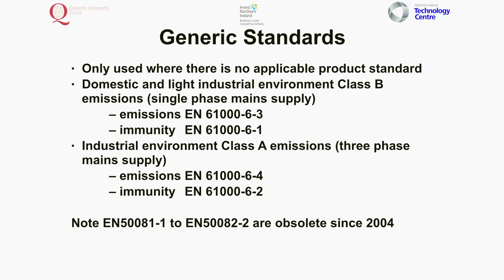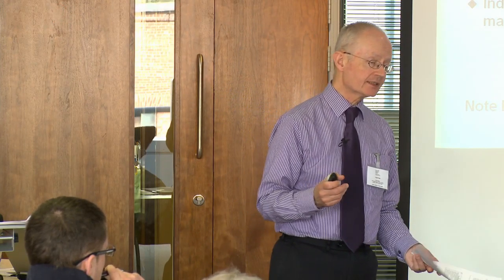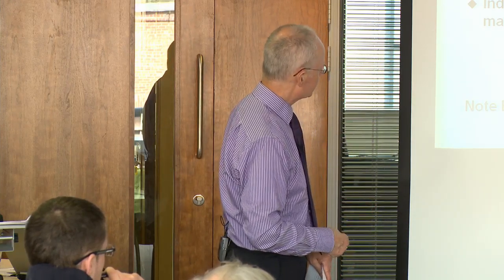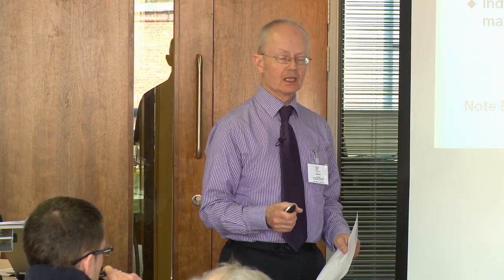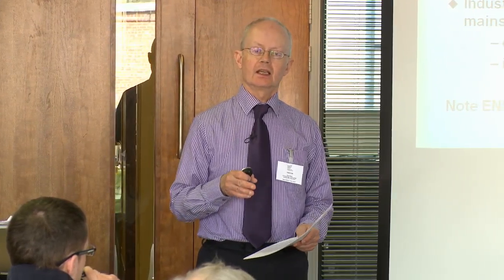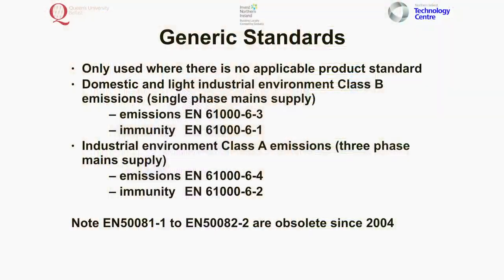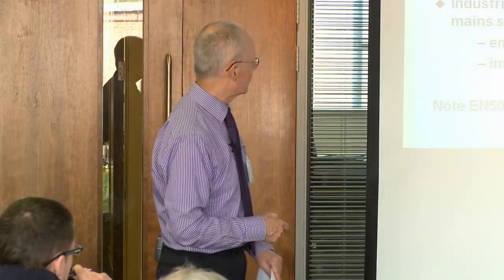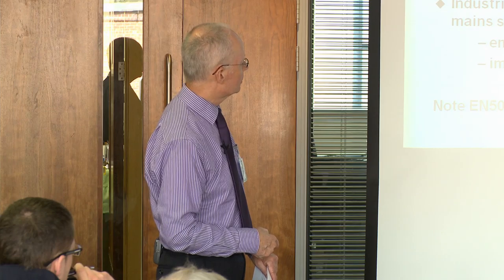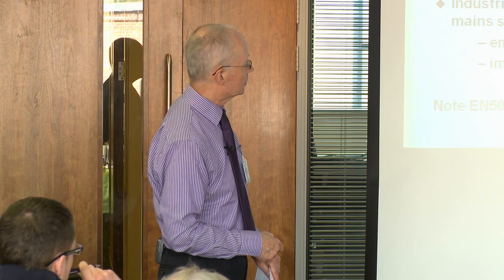If you can't find a product standard, then the default is to go to the generic standards. You only use those when you can't find the appropriate standard, and luckily there's only four of those. They break down into the domestic and light industrial environment, which for emissions is Class B. As a simple definition: if it's going into somewhere and supplied from a domestic mains socket, the chances are it's going to be Class B.